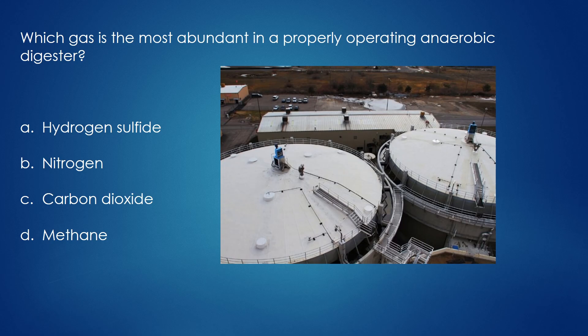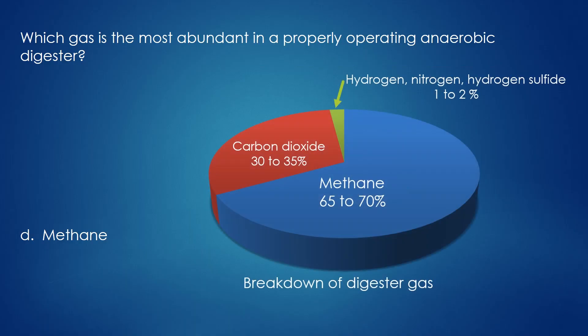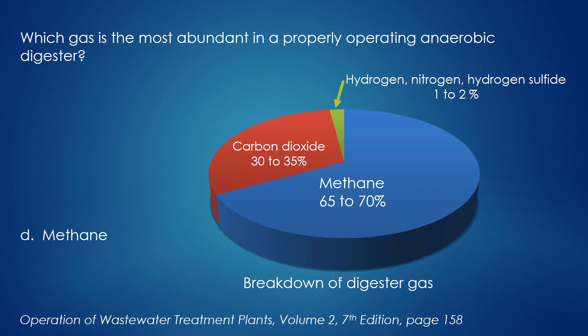Which gas is the most abundant in a properly operating anaerobic digester? Methane. The digester gas is mostly methane — 65-70% of the digester gas is methane. The second most abundant gas in the digester is carbon dioxide at 30-35% by volume. The remaining 1-2% consists of gases such as hydrogen, nitrogen, and hydrogen sulfide. To learn more, go to the textbook Operation of Wastewater Treatment Plants Volume 2, page 158, for more detail.